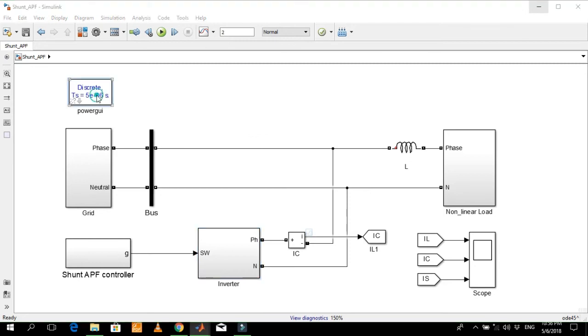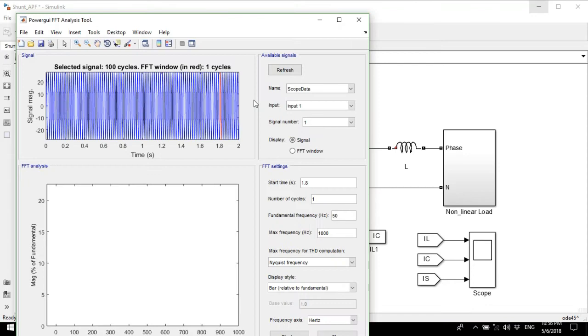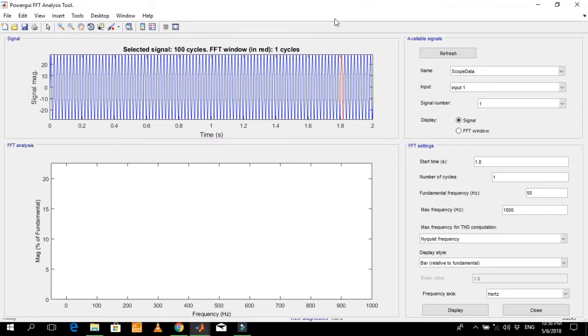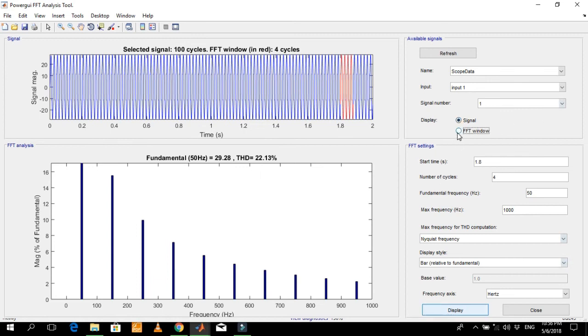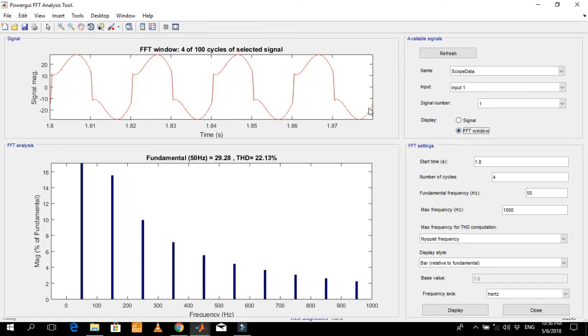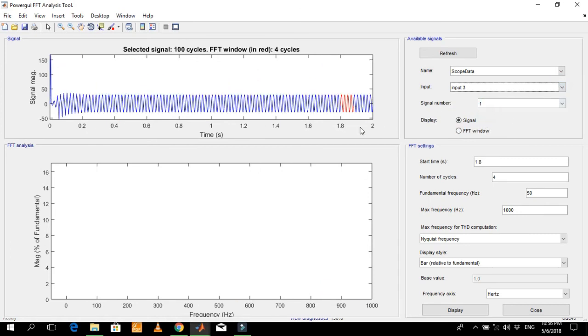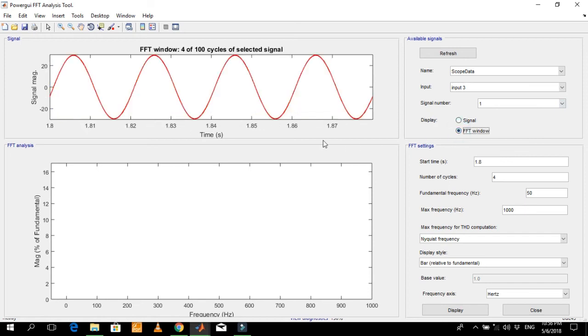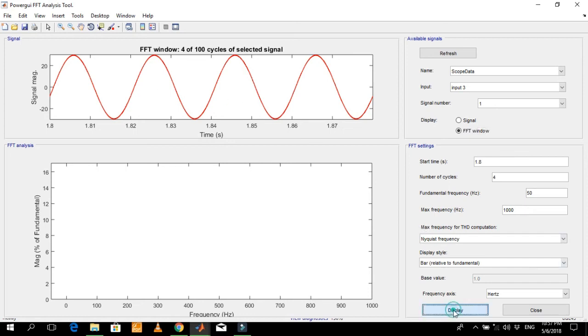Let me show you the THD of the load and source currents. This is the load current — the THD of the load current is 22.13% of the fundamental component. This is the source current — its THD is just 1.67% of the fundamental component.